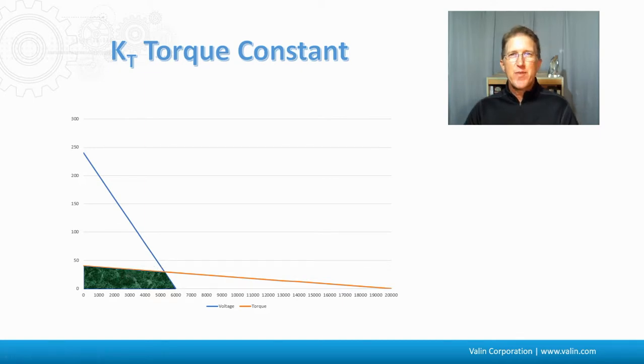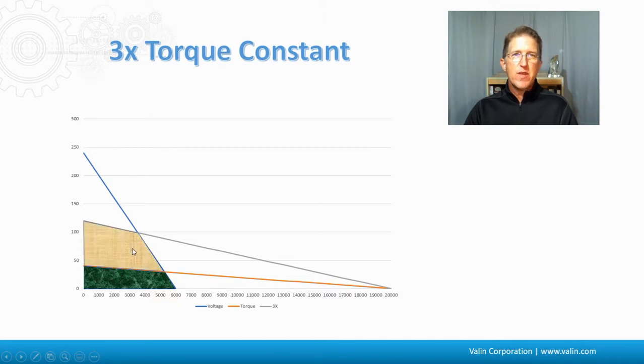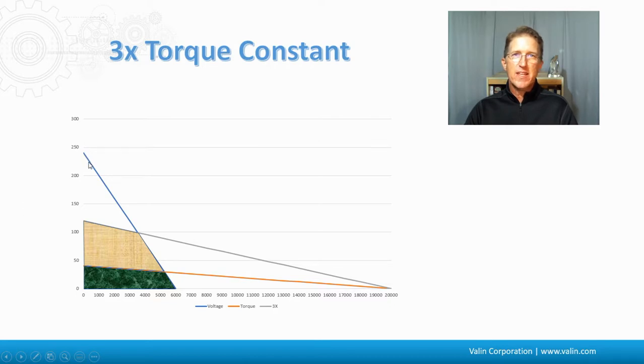The peak current is defined by assumptions made by the designers. Typically in the industry it's three times the continuous rating. If we plot a 3X curve, that represents three times the continuous capability. We could potentially go higher, but it would be for a very short duration. Sometimes you see a 2X curve instead. What you end up with looks like the speed-torque curve — continuous here with a peak here, and a slope defined by the back EMF.